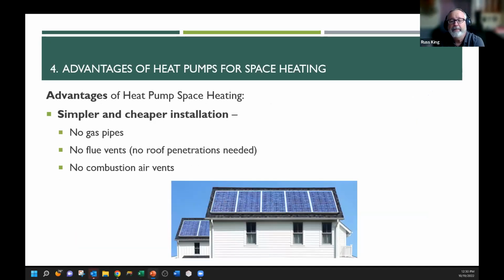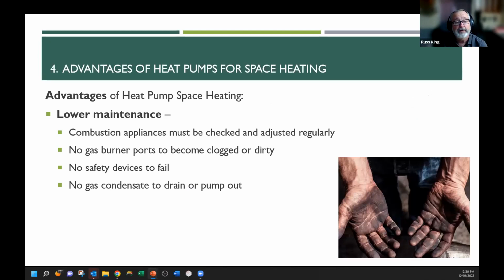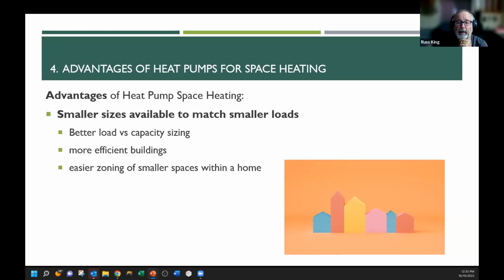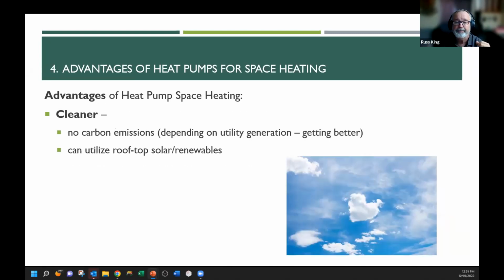The other advantages: simpler and cheaper, no gas pipes, no flue vents, no combustion air considerations. It's a lot easier to put in electric heat pumps than it is to put in gas heat. Lower maintenance, that's a big deal. Open up your furnace and look inside, if you have a gas furnace. 90% of the things you see in there are safety things. Those all have to be calibrated, and they all go bad. Another advantage of heat pumps is smaller size. If you have a really small ADU, or a really small dwelling unit, heat pumps come in much smaller sizes that are more appropriately sized to those small dwelling units.